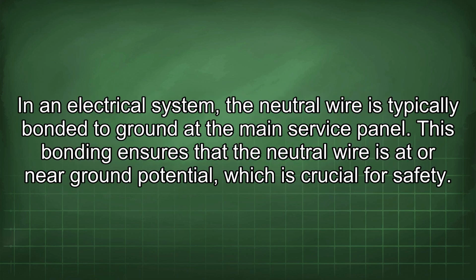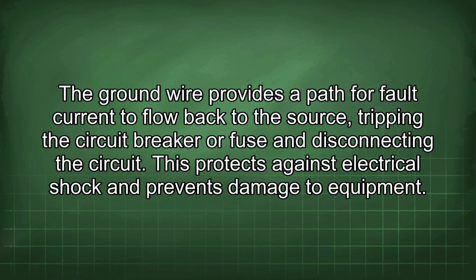In an electrical system, the neutral wire is typically bonded to ground at the main service panel. This bonding ensures that the neutral wire is at or near ground potential, which is crucial for safety. The ground wire provides a path for fault current to flow back to the source, tripping the circuit breaker or fuse and disconnecting the circuit. This protects against electrical shock and prevents damage to equipment.